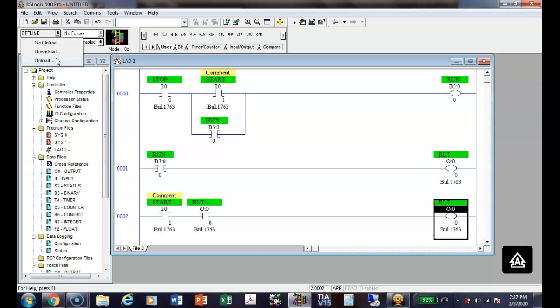It's going to take whatever program that's currently in the PLC and it's going to go there. And that could wipe out your current program, right? You understand? So, there's a ton of difference. If I want to send something to the PLC, I want to download. If I want to bring something from the PLC and bring it into my programming application, you do upload. So, that gets you messed up. I've done that before. I've wiped out a program.